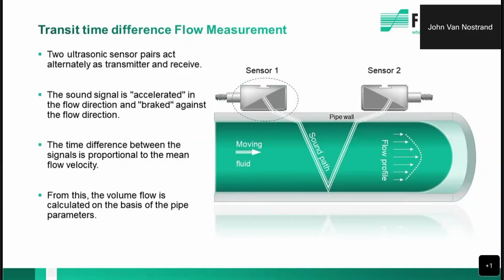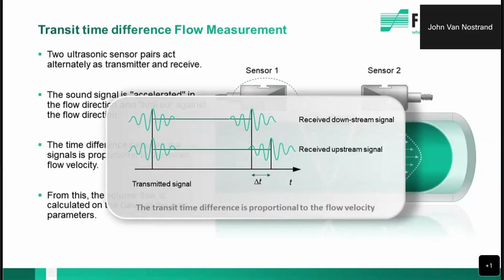Transit time meters, as the name implies, measure the difference in time travel between the ultrasonic pulses transmitted in one direction with the flow and against the flow. And we're measuring the time difference between the two, shown here. The top sinusoidal waveform is the energy traveling from the upstream transducer to the downstream transducer, and the bottom sinusoidal waveform is the energy traveling back. It's the difference in time between the two that we're measuring, and that is proportional to the velocity of the media. We know the diameter of the pipe, so therefore we calculate volumetric flow.